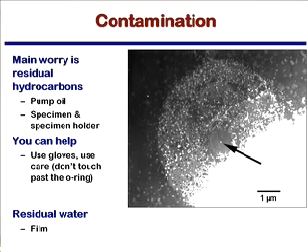In other words, you have to be aware of the fact that your electron beam can contaminate your sample and change things about what you're imaging. And so if you have a better vacuum, then you are in better shape, okay? You can help things with this. Again, if you follow proper procedures, if you make sure your sample is clean at the end of the sample preparation process, if you use, say, gloves to make sure that you don't touch past the O-ring, if you're just careful about not touching past the O-ring of the sample holder, that can help.